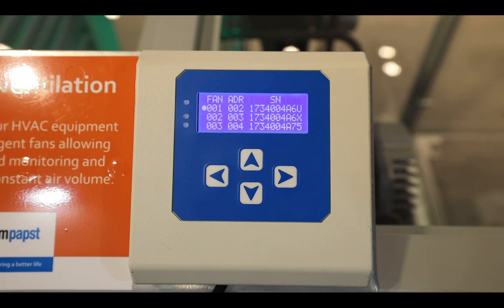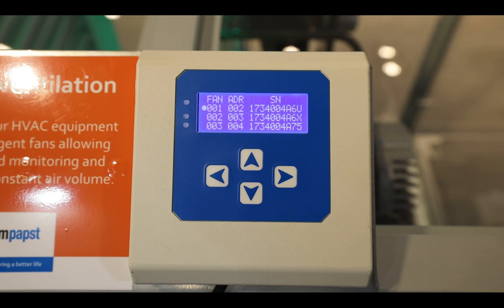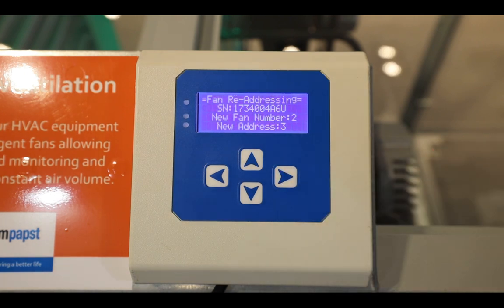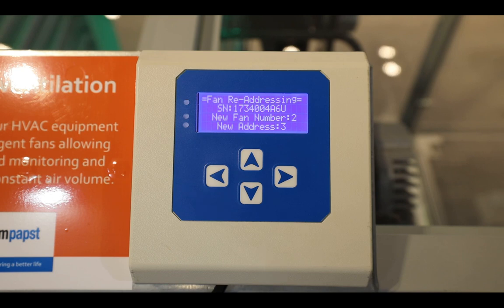Fan 1, with serial number ending A6U, has Modbus Device Address 2. Fan 3, with serial number ending A75, has Modbus Device Address 4. To change the position of fan 1, it first must be selected. By selecting this fan, the controller automatically selects the destination as logical device address 2 and Modbus Device Address 3. The network destination needs to be changed in this case to fan 3 and confirmed to carry out the change.